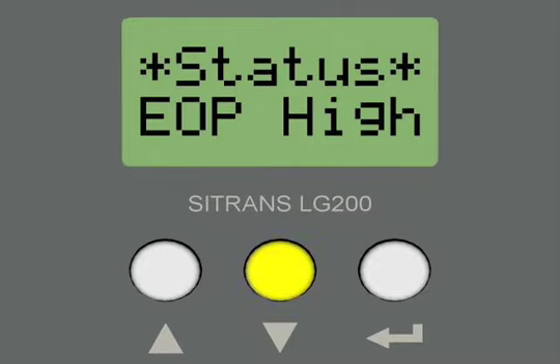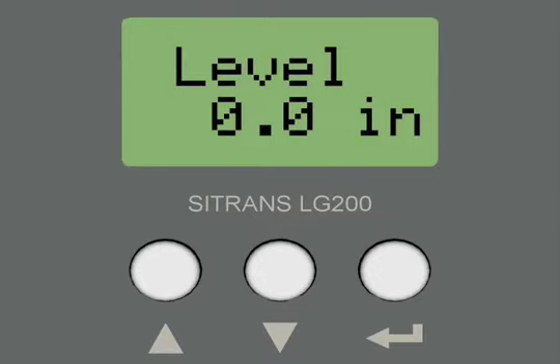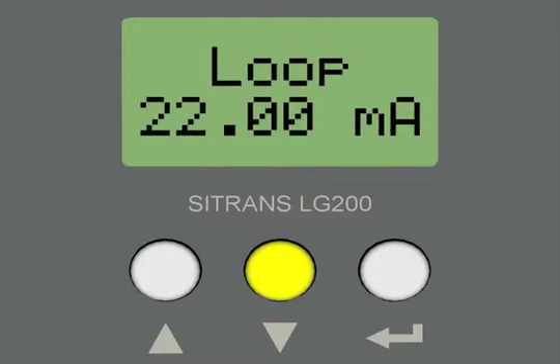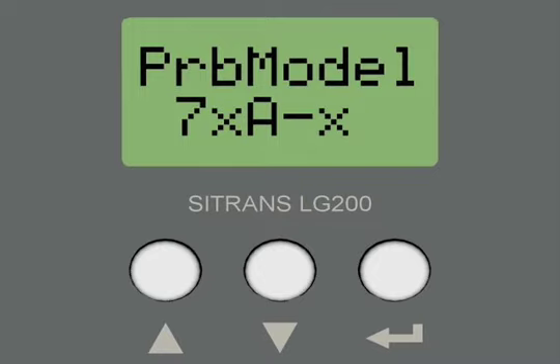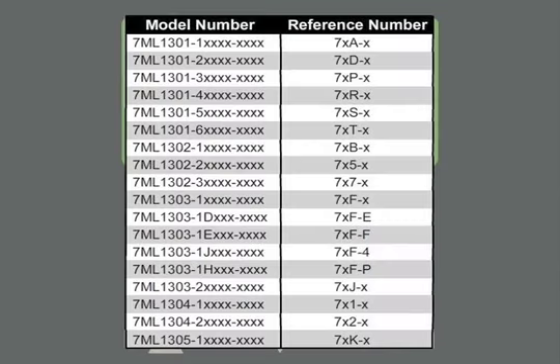Press the down arrow key to enter program mode. The first 3 screens are run mode information. These values can be ignored at this time. Push the down arrow key 2 more times. The first parameter to modify is the probe model parameter. To set this parameter, you will have to consult the manual and the nameplate on the probe. According to the manual, there are 18 probe model selections. To select the correct probe model reference number, we will use the model chart.